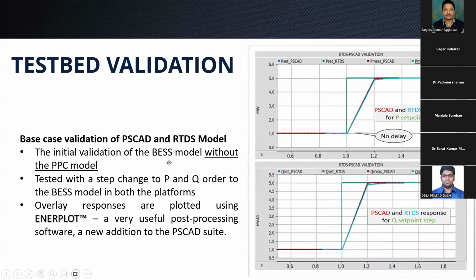There will always be some differences, because you are using a physical device which has something called a communication unit. If you are using a communication protocol, it will have certain delays, which are not part of a PSCAD simulation. So you have to measure that delay with the RTDS setup and model that exact same delay into PSCAD using the delay component. Once you know the delay, you model it, and then the responses can be compared.